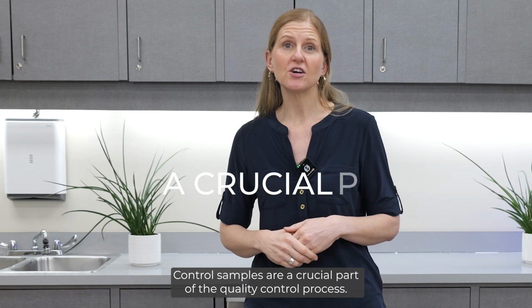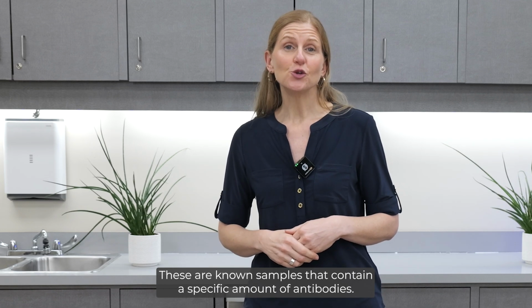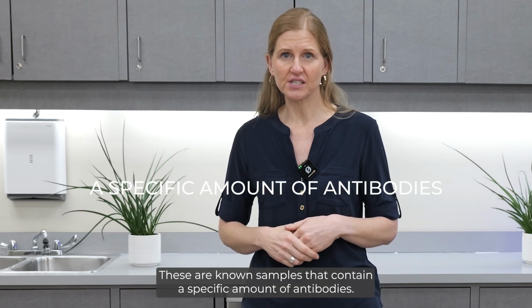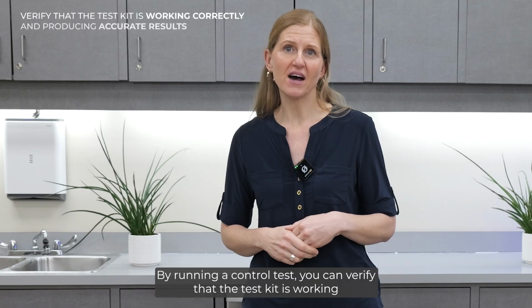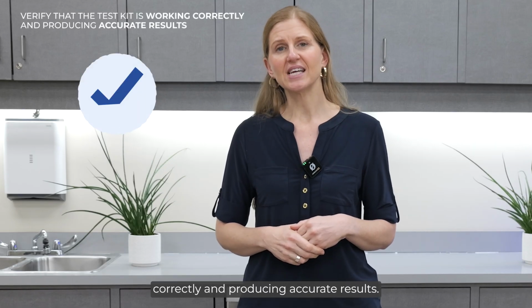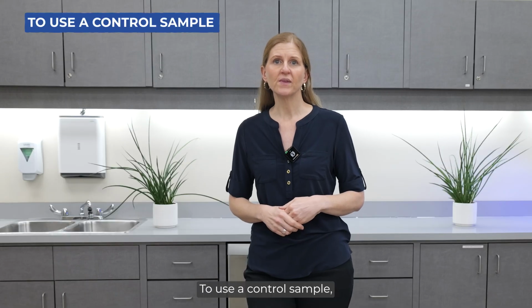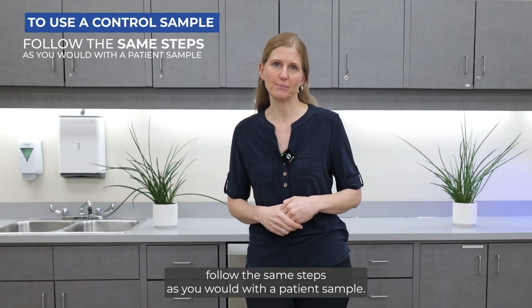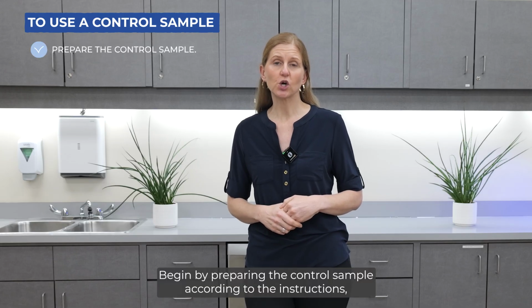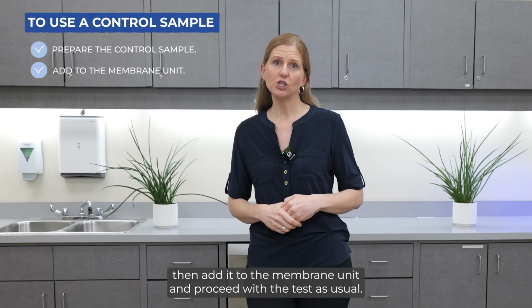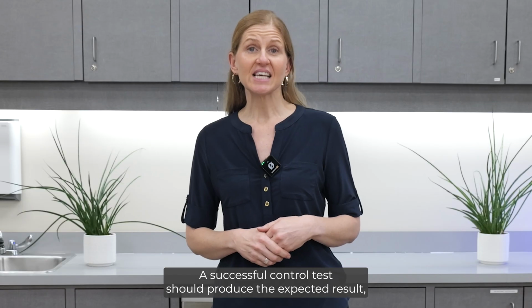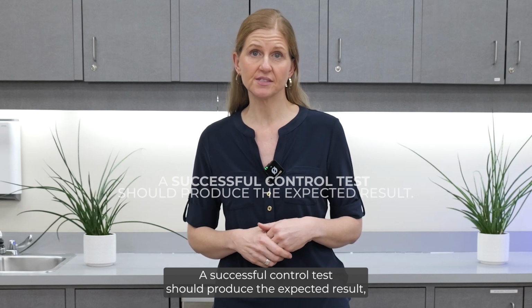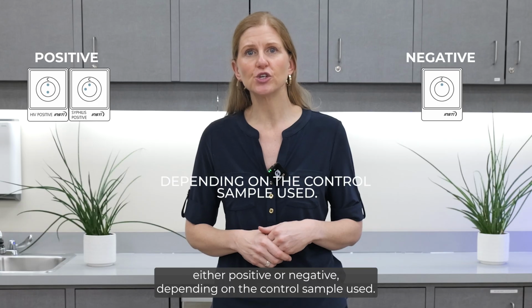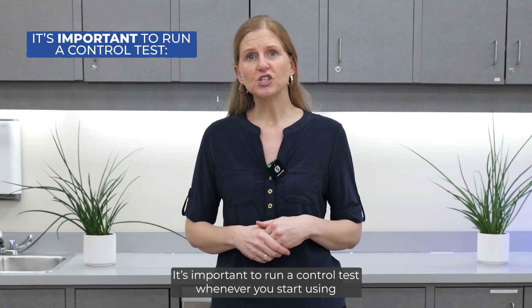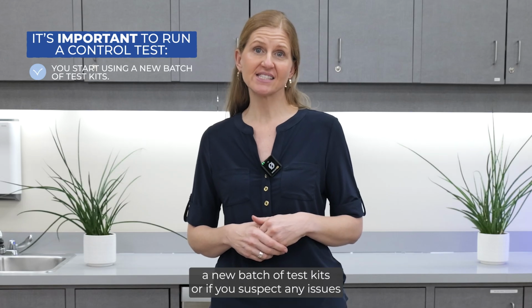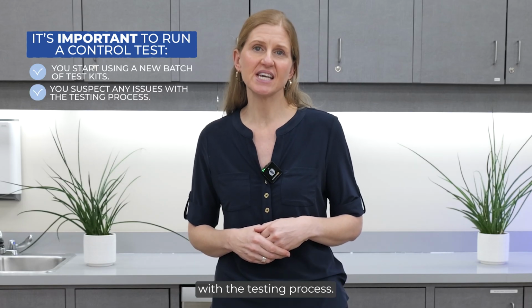Control samples are a crucial part of the quality control process. These are known samples that contain a specific amount of antibodies. By running a control test, you can verify that the test kit is working correctly and producing accurate results. To use a control sample, follow the same steps as you would with a patient sample. Begin by preparing the control sample according to the instructions, then add it to the membrane unit and proceed with the test as usual. A successful control test should produce the expected result, either positive or negative depending on the control sample used. It's important to run a control test whenever you start using a new batch of test kits or if you suspect any issues with the testing process.